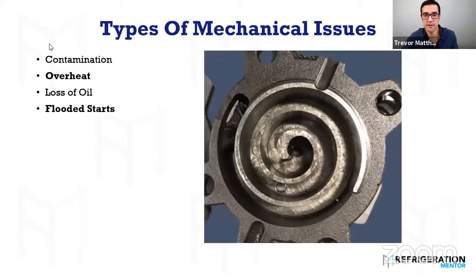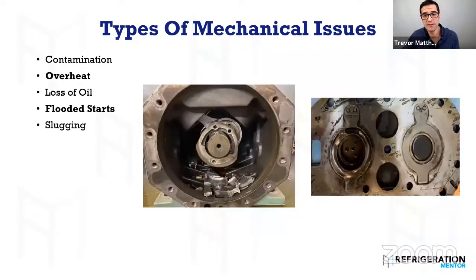Let's see what else we got here. Flooded starts. This one is a big one. How do flooded starts happen? Really, it happens through what we call refrigerant migration. That compressor's off. The compressor's the coldest part of the system. That refrigerant travels through the system as a vapor, condenses in the oil, and then when that compressor starts up, boom, you have a flooded start, or it leads to what we call slugging. Slugging in refrigerant cooled compressors is from major flooded starts. Slugging in air cooled compressors is from uncontrolled oil return or liquid floodback. And you need to understand the differences.